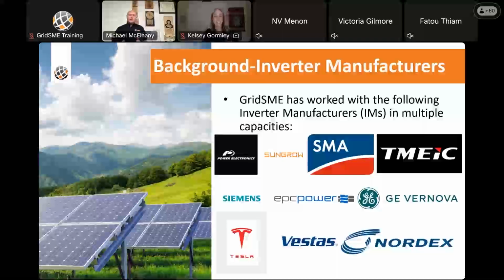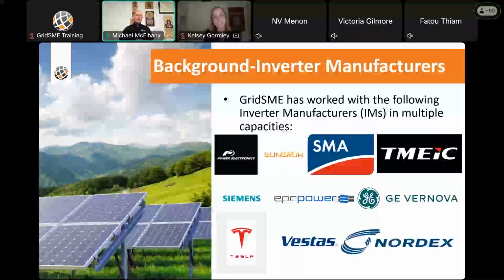So as a lead into this section, I just want to let you know that GridSME has had significant interaction with all of these inverter manufacturers. In 2023, I did 25% of all the facilities that submitted information for the inadvertent tripping NERC alert. In 2024, we did even more, almost doubled the number of plants that we did for the modeling deficiencies NERC alert. So we've worked with all of them, and that's how I became the inverter guy for GridSME. I've got contacts at each one of these inverter manufacturers, and work with them very closely whenever we run into something new with CAISO.